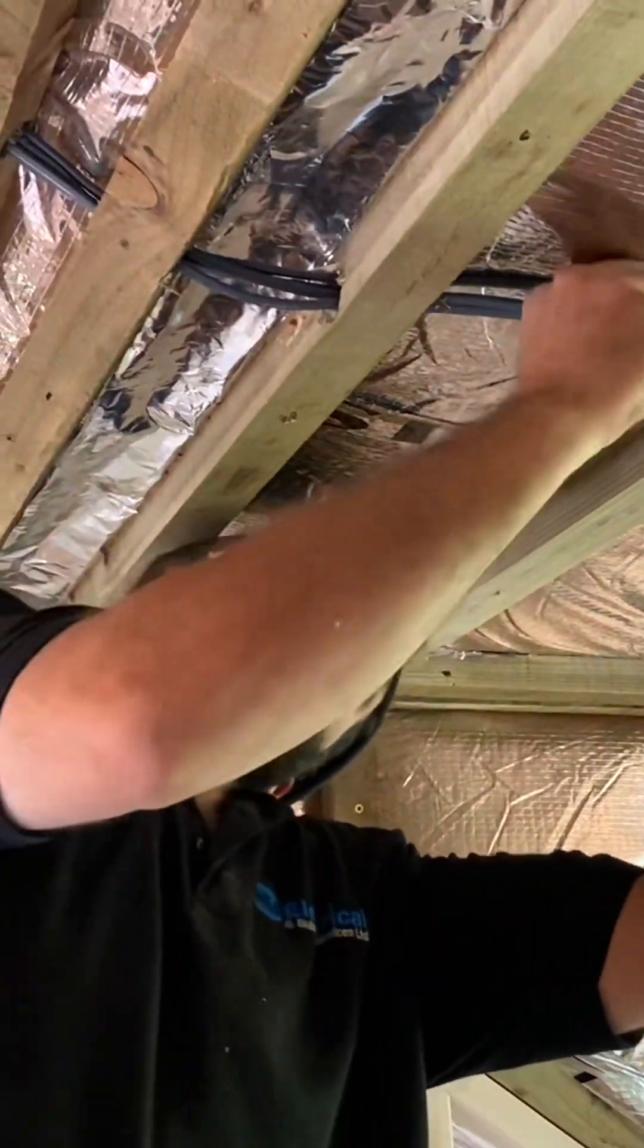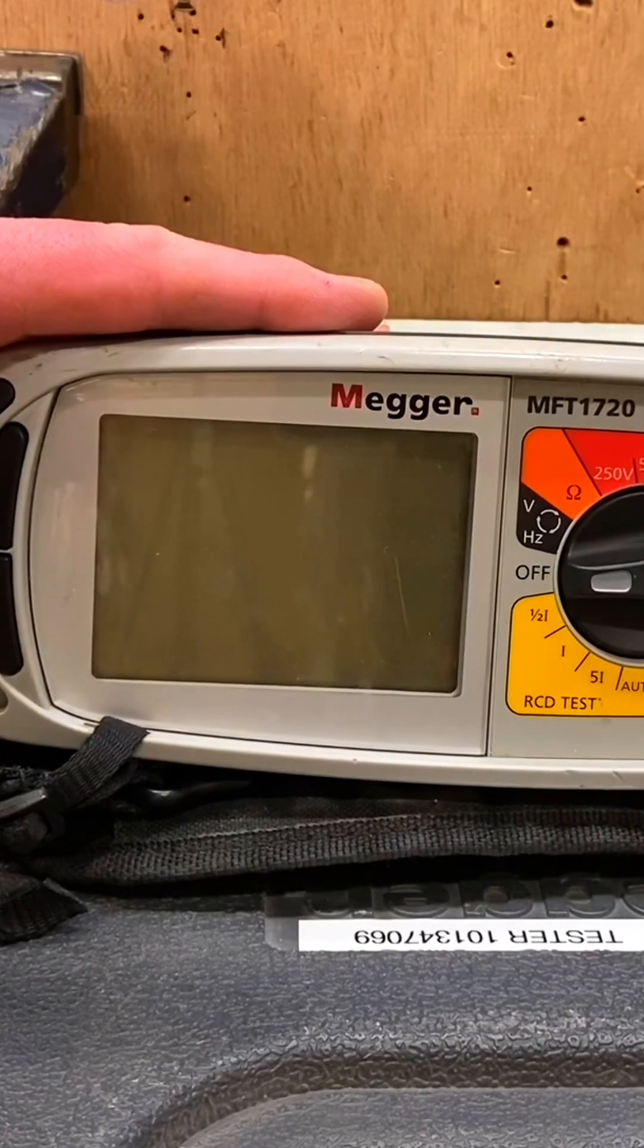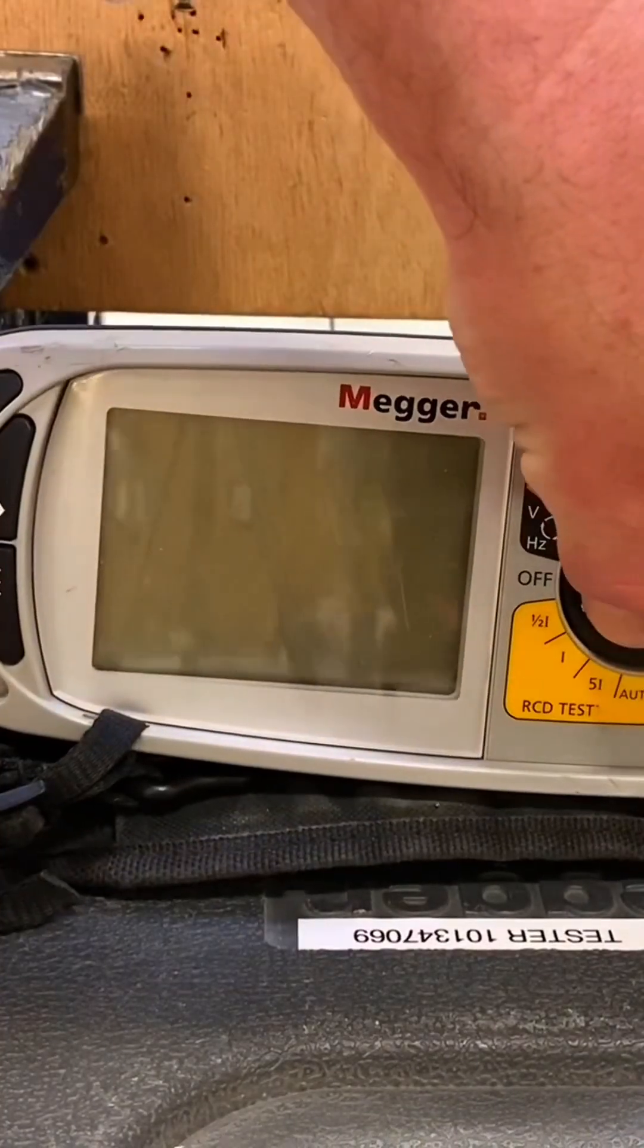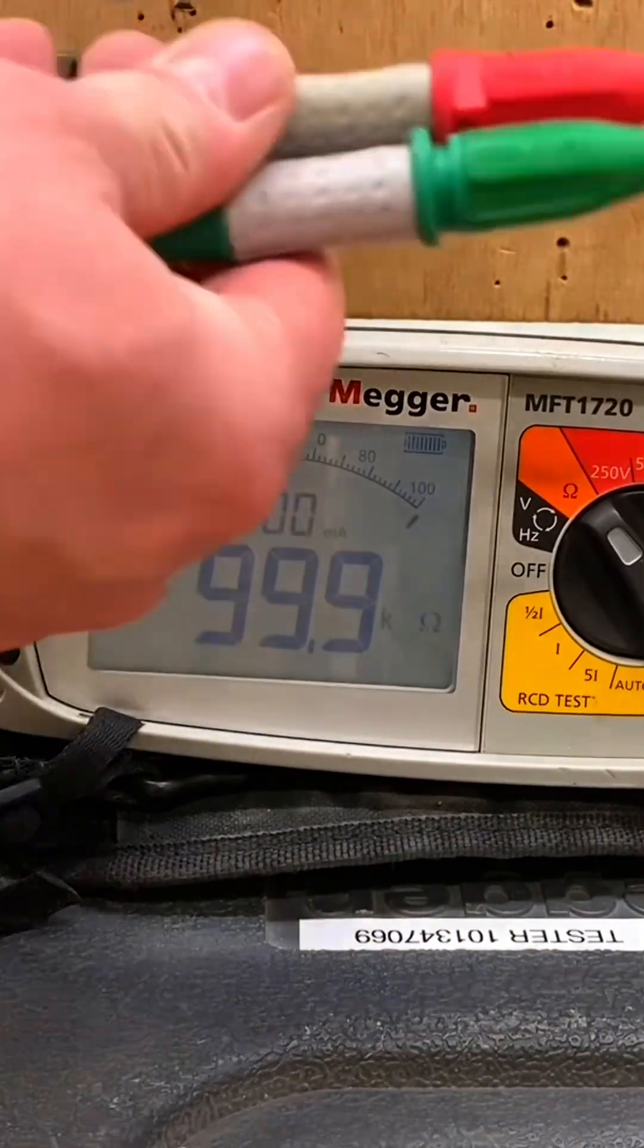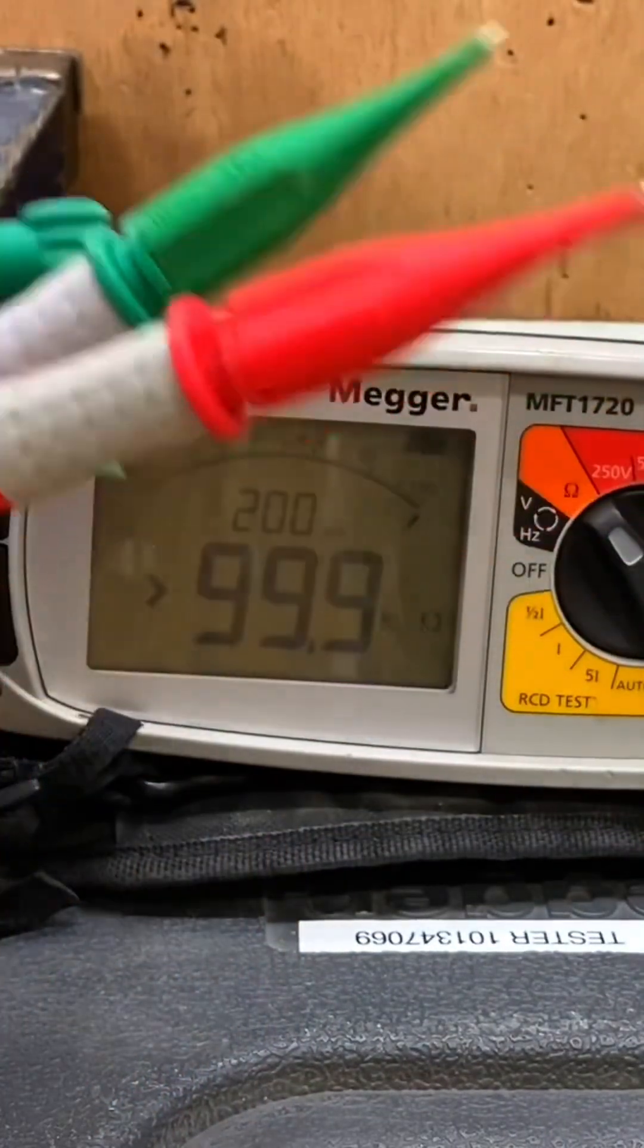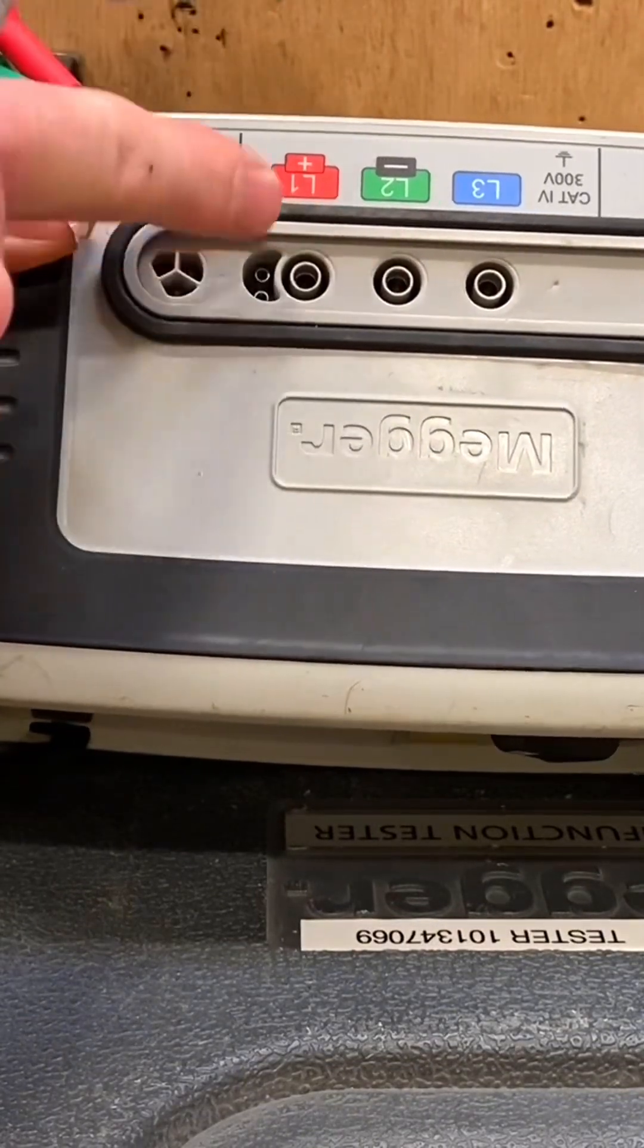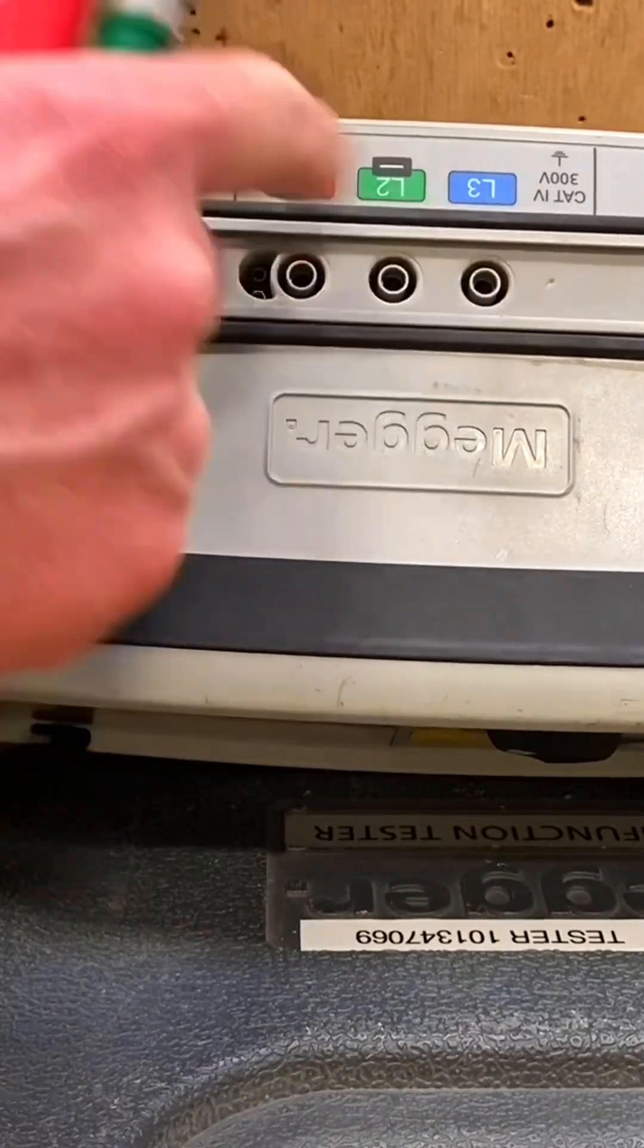Let's set up our Megger MFT to measure the continuity of the CPC test. We're measuring the resistance of the conductor, so we need to move it to the orange scale for ohms. We insert our leads - we generally use the red and green ones in the correct slots at the top. We ignore the blue one at this stage, we'll get back to that on the level three apprenticeship.